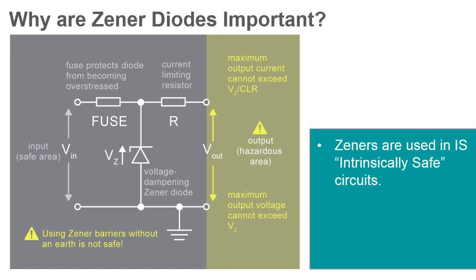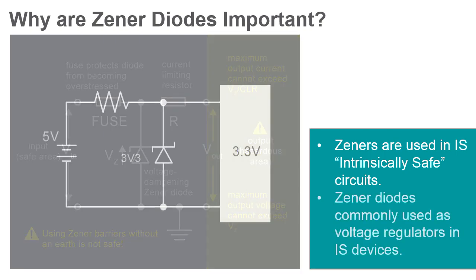Zener diodes are important components in intrinsically safe circuits. One of the most common methods of protection is to limit electrical current with multiple resistors in series and to limit electrical voltage with multiple Zener devices to ground. Equipment and instrumentation specifically designed for use in hazardous areas usually operates with low voltage and current. In addition to the protection from over voltage, Zener diodes are used to regulate the operational voltages of these devices.